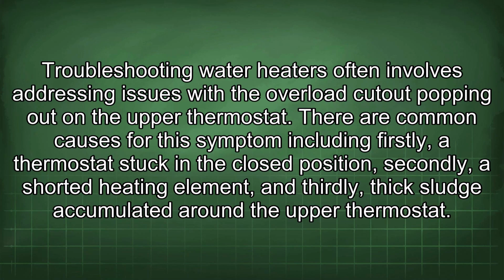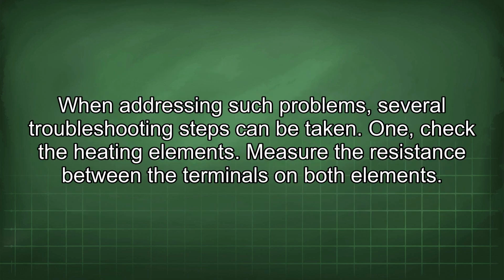Troubleshooting water heaters often involves addressing issues with the overload cutout popping out on the upper thermostat. There are common causes for this symptom, including firstly, a thermostat stuck in the closed position, secondly, a shorted heating element, and thirdly, thick sludge accumulated around the upper thermostat. When addressing such problems, several troubleshooting steps can be taken.